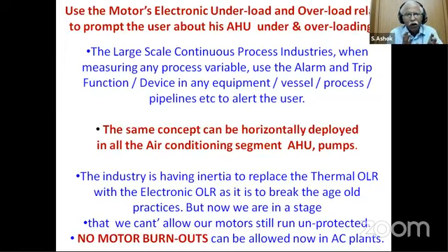It's fine, but for all the AHUs and pumps, if this electronic motor protection relay is fitted instead of the thermal OLR, definitely we can know whether the pump is running at normal load, overload or underload. A blower which is running at underload is a cause of concern, especially in post-COVID times when the air circulation is less and the air thrown from the blower is less. Definitely the IAQ of the air conditioned premises is put to task. It is going to vary very badly.